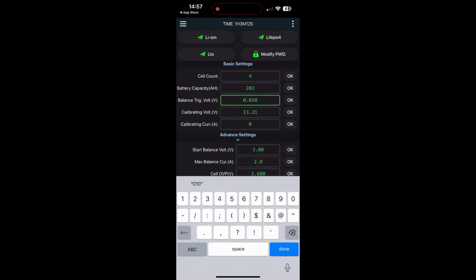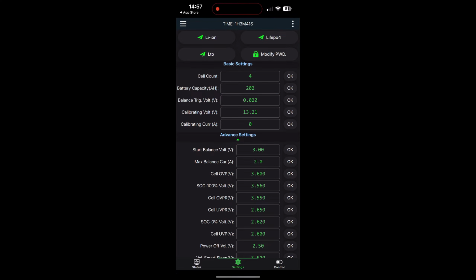The next setting, balance trig volt. What this is, is what voltage difference between the cells do you want to have before the balancer kicks in. In other words, in this instance, if the biggest variance between the highest charged cell and the lowest charged cell is more than 0.01 of a volt, then the balancer will start. If it's less than that, the balancer will stay inactive. Okay, I'm happy to leave it at that, or if you wanted to change it to, say, 0.02, you can go and change that.